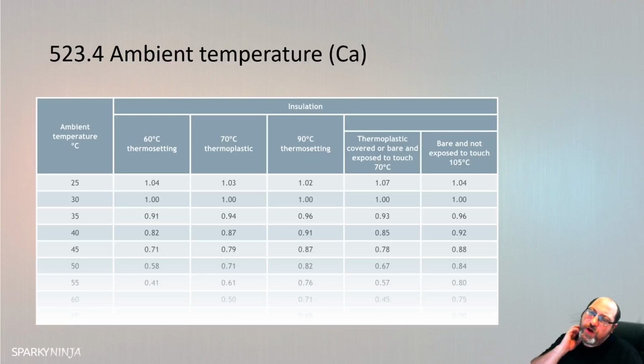Do remember that overload only occurs on socket outlet circuits or motor circuits, equipment that can overload in a fault-free condition. It's not fault protection, it's overload protection. We're going to remind ourselves of that, because soon I'll be saying, is our load likely to overload? Yes or no, and that will depend on if we use that factor, if the protected device is a 3036.